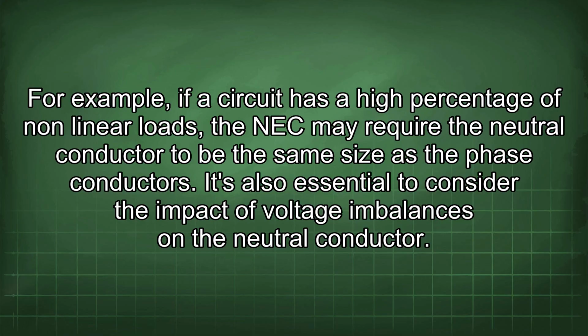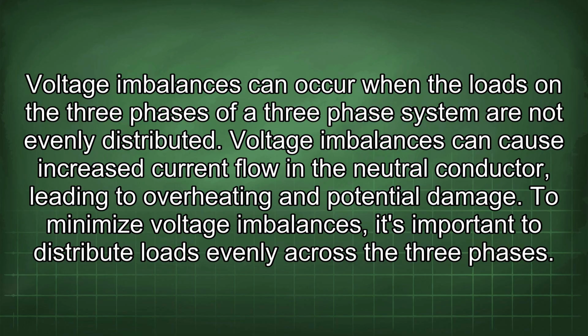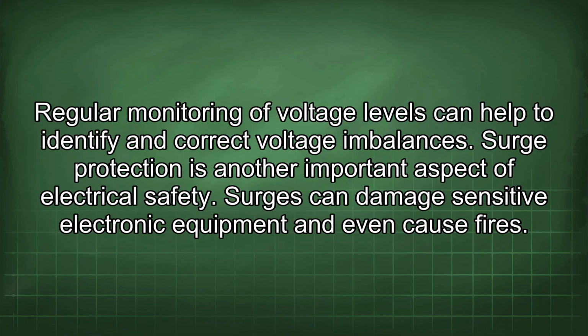It's also essential to consider the impact of voltage imbalances on the neutral conductor. Voltage imbalances can occur when the loads on the three phases of a three-phase system are not evenly distributed. Voltage imbalances can cause increased current flow in the neutral conductor, leading to overheating and potential damage. To minimize voltage imbalances, it's important to distribute loads evenly across the three phases. Regular monitoring of voltage levels can help to identify and correct voltage imbalances.